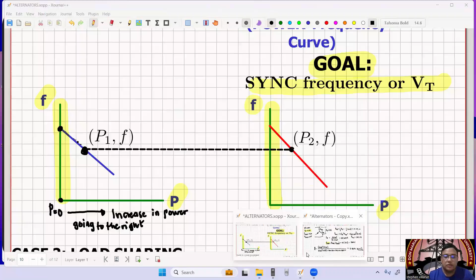Let's try answering this. Number 30: adjustment of field excitation on one of two alternators operating in parallel will do what? Take note, when there's an adjustment to the field excitation, we will change the power factor of the system. This is similar to what we discussed about synchronous motors - when normally excited, unity power factor; under-excited, lagging power factor; over-excited, leading power factor.